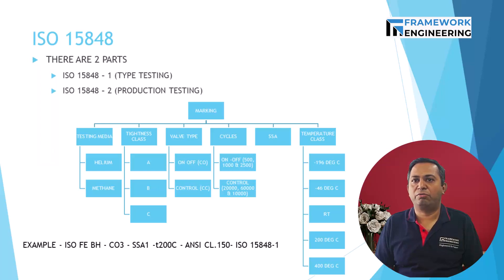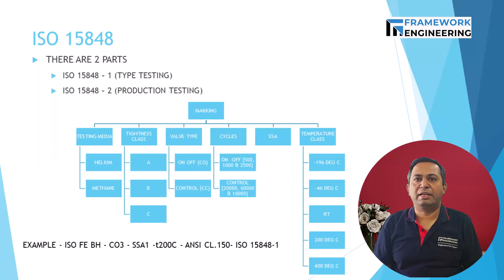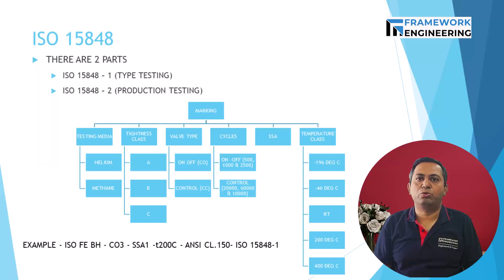If it is an on-off valve, the number of cycles are 500, 1000, and 2500. If it is a control valve, then the number of cycles are 20,000, 60,000, and 100,000. Next is SSA — that is stem seal adjustment — and then the temperature class, indicating up to which temperature you need to qualify.